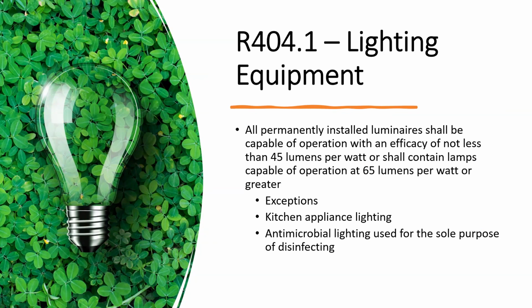Before it was always that kitchen appliances are exempt from lighting requirements if installed per manufacturer. So if you've got lighting on a vent-a-hood, on a stove, or on a microwave, those lights are exempt from having to meet that 100%. And also they're exempt from having to meet this lumens per watt requirement as well. But now what they did was add antimicrobial lighting used for the sole purpose of disinfecting. So if some people are installing these in their homes, where you've got lighting that will disinfect, those things are also exempt. But that requirement of 45 lumens per watt or 65 lumens per watt for operation was the same.